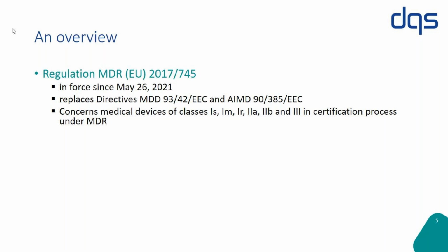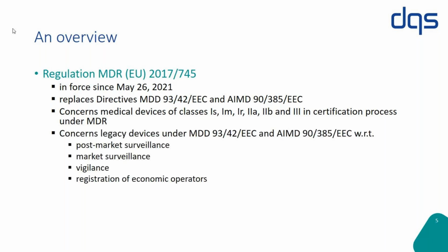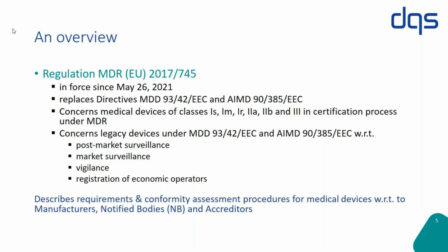Besides the newly requested medical devices, we also have legacy devices, certified and implemented on the European market under the directives MDD and AIMD, which concerns requirements with the post-market surveillance, market surveillance, vigilance, and the registration in the new database. The European Medical Device Regulation describes the requirements and the conformity assessment procedures for medical devices for three parties: the manufacturers, the notified body itself, as well as their accreditors.